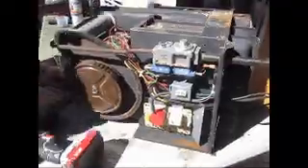Yeah, we got the fan cover off. We're trying to remove the squirrel cage unit from the rest of the furnace. We got all these screws taken off just to expose this. There were a bunch of dead flies in there. You can see in here when I'm moving the squirrel cage, look at all the crud that's just moving around inside there. All the fiberglass, and there's all this peeled paint, which we'll fix once we get the unit off. There's all this corrosion here, which we're going to have to scrape off and clean up as well.